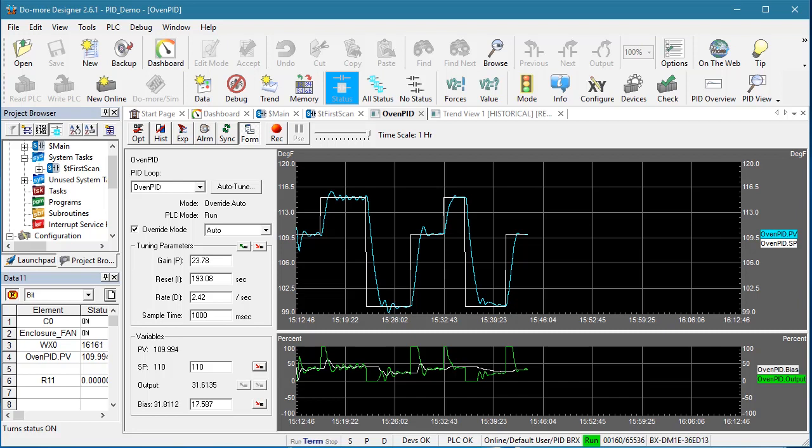And in general, you'll find that temperature PID applications will almost always work better with the full PI and D coefficient set, while just P and I will usually be fine for most other industrial applications.